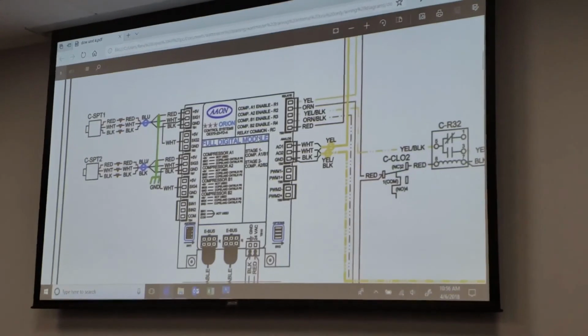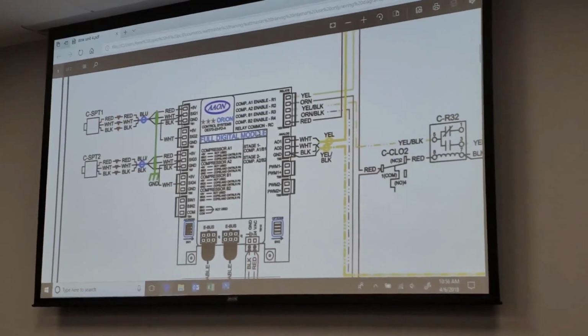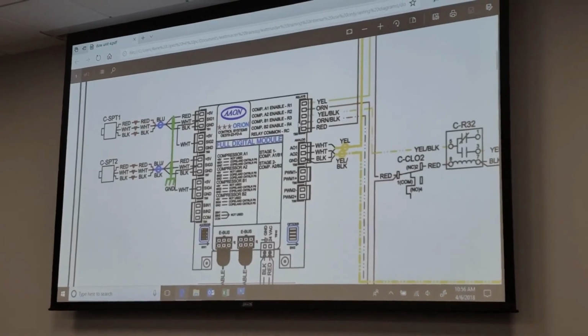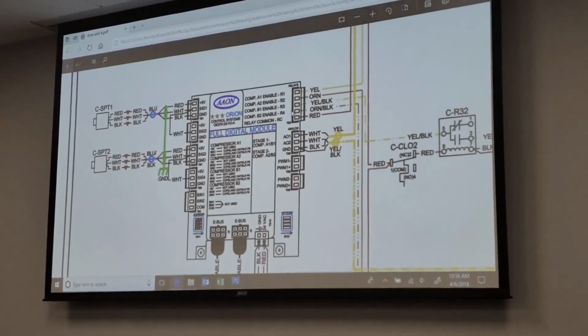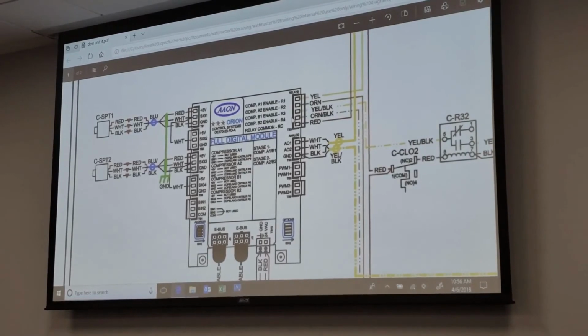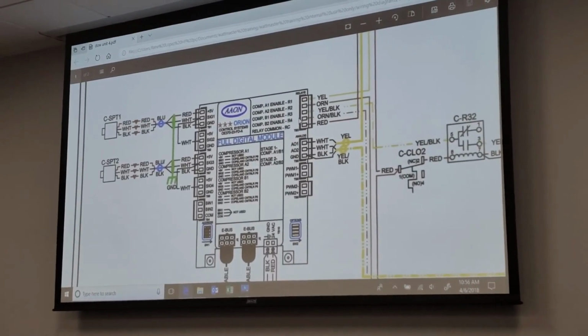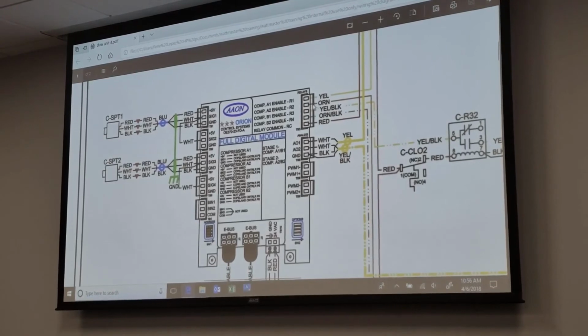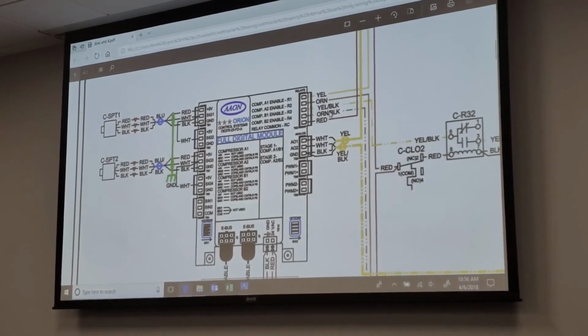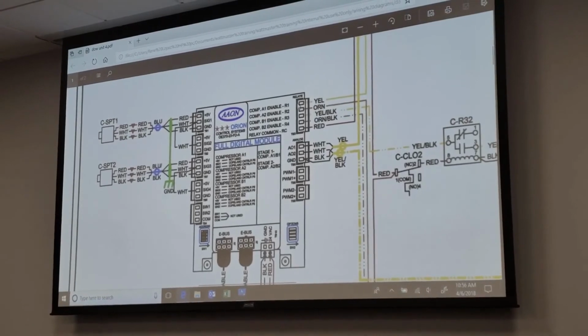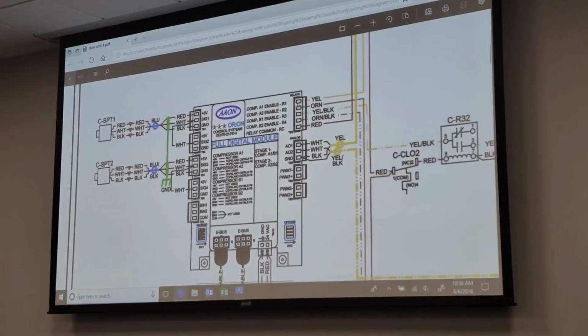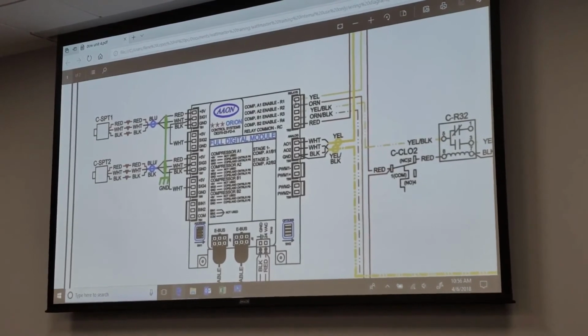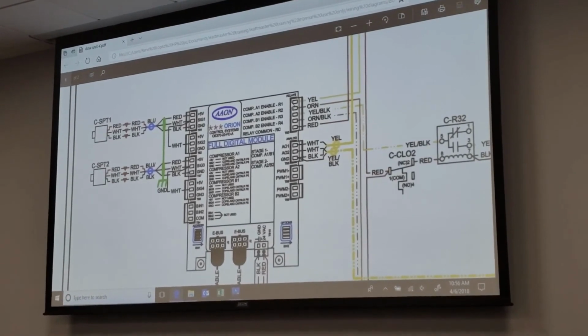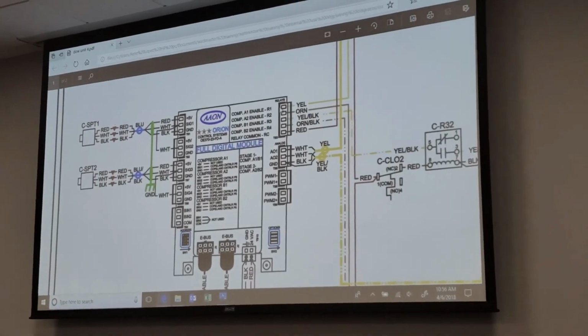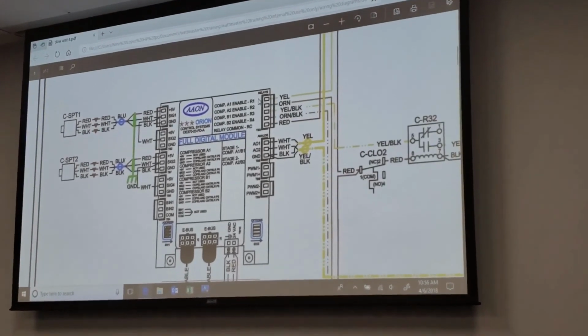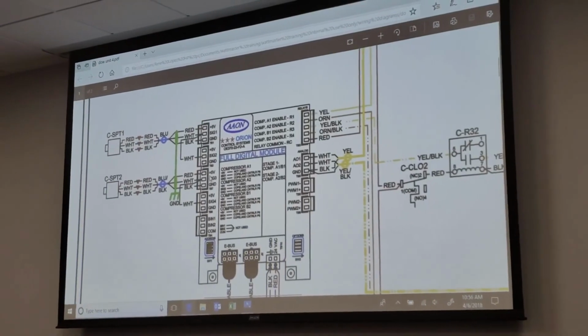So when they replaced the board, that's when they found it? No, we did startup on it, and we found that the compressor kept tripping. Then we went back and looked at it and went, hey guys, these should be swapped. The orange and black, this orange wire belongs in terminal 3, and the yellow and black belongs in terminal 2. Those two needed to be inverted because they changed the code. That was the old code right there; that's how it was supposed to be. The new code is 1 and 2 come on together, and then 3 and 4 come on. I seen that on something.